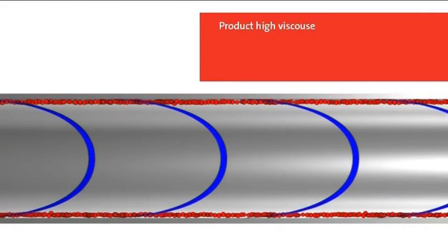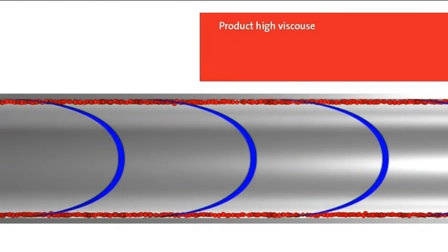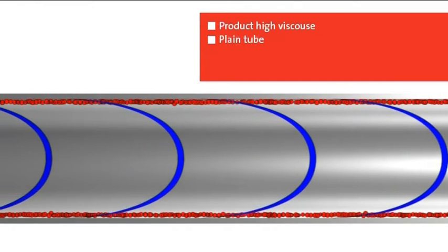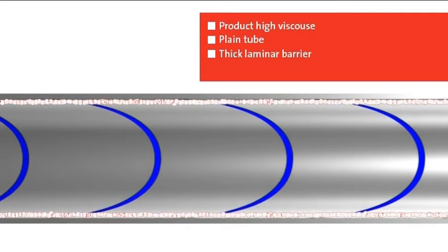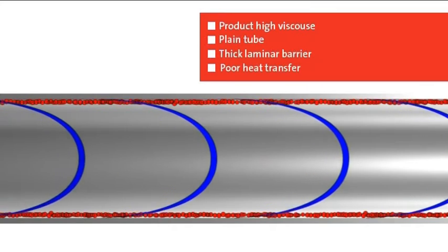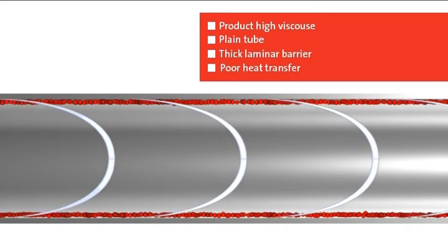Now we see a high-viscous product in a plain tube and a very thick laminar barrier. The heat transfer is here significantly poorer by reason of different velocities and different temperature layers. The poor heat transfer achieved means that the product is not being adequately treated.